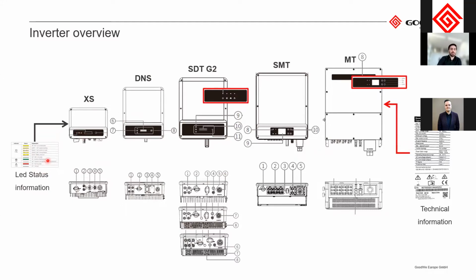And this can be very good to read. This is also included in the manual. In case something doesn't work or during the installation, you are wondering how it progresses, then you can check the LED lights here to check if it's connected to the AC side, if you have DC connection, if the Wi-Fi works, etc. And on the right-hand side of the inverter, you have also a sticker showing some information about your specific inverter. And in case of any warranty issues or issues with the inverter, you need to contact after sales. The sticker here on the side is really good to have a picture of. So I could recommend you that during installation, take a picture and save it. And this could be used for future purposes.